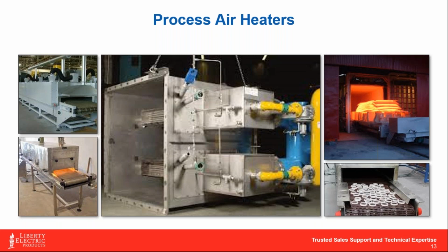product. Electric air heaters, however, can also be extremely precise in their temperature control, which is a big attraction to these as well, in that they're excellent at maintaining within 1 degree set points versus gas units. So it's really more of an application-driven thing.